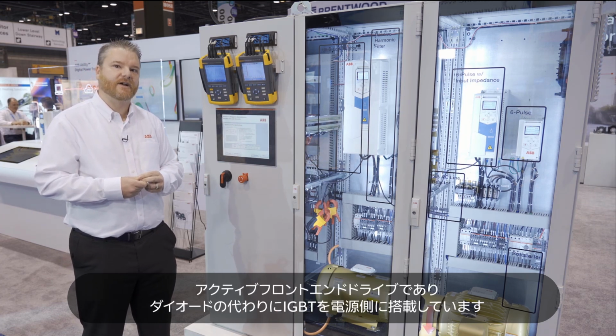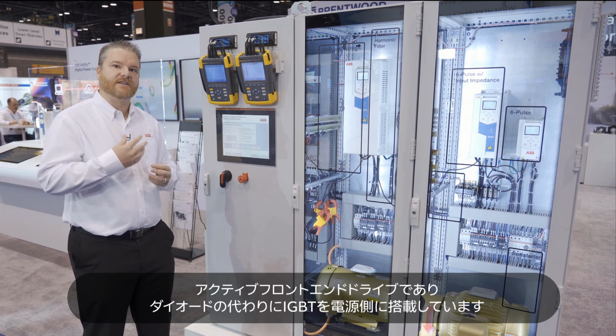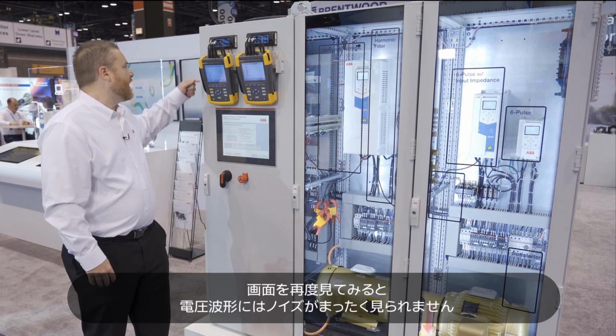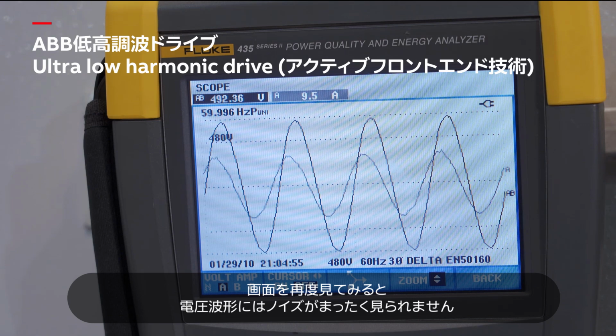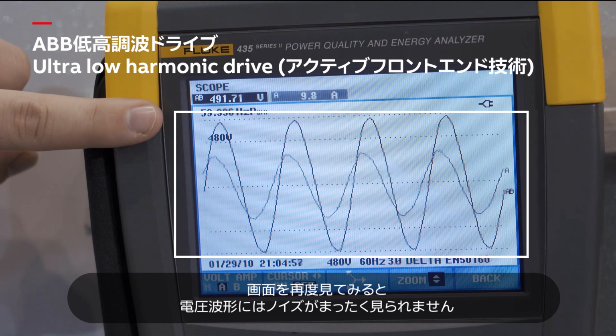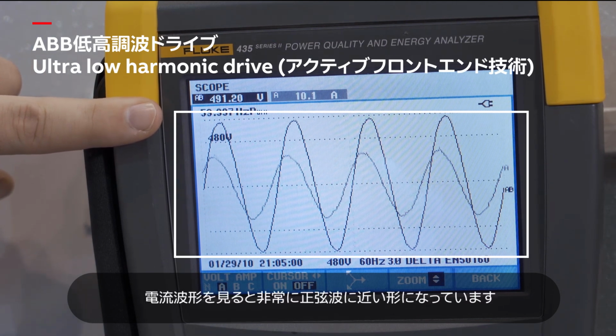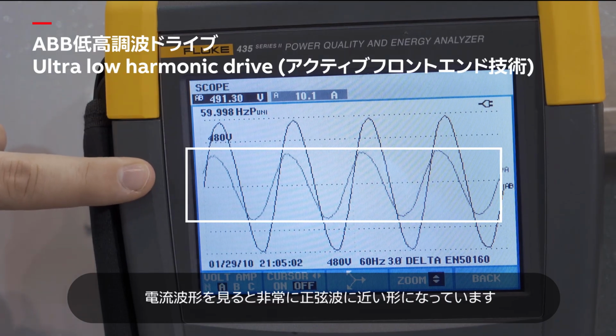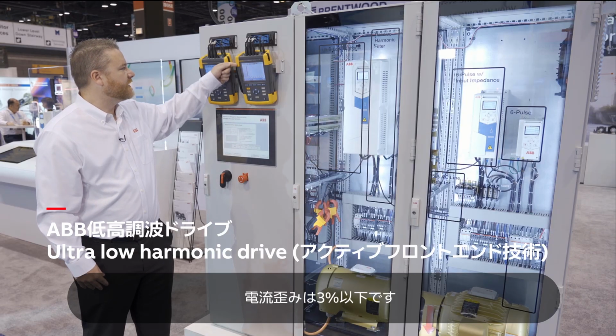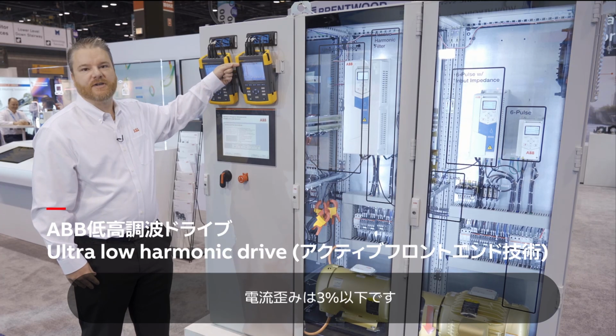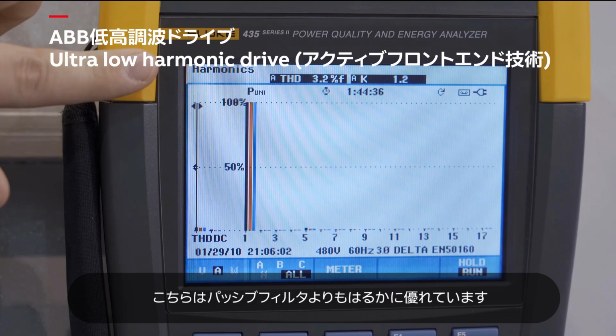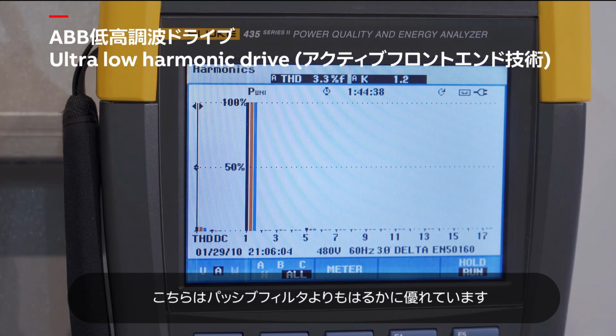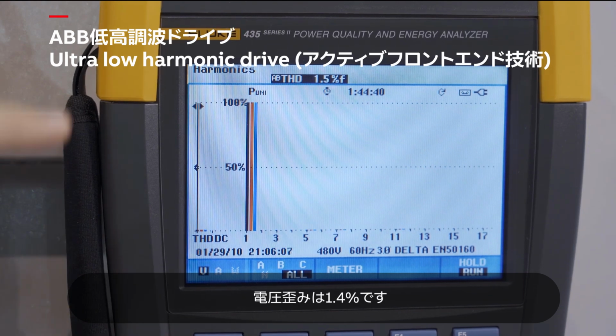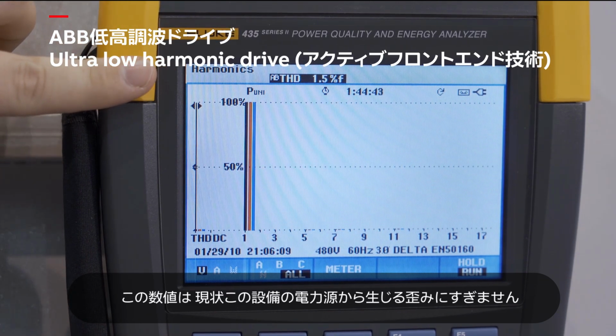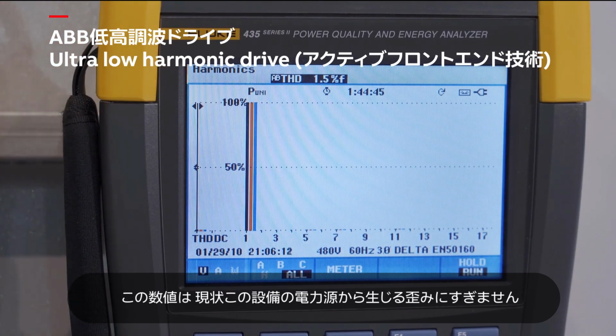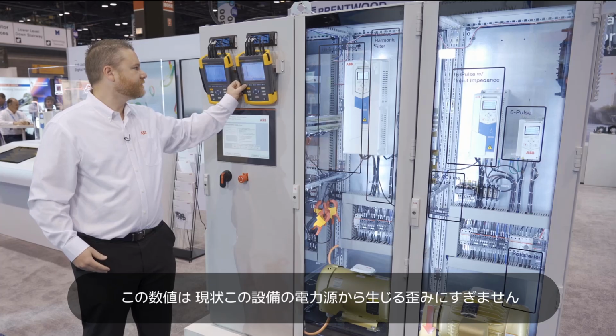This is an active front-end drive. So instead of using diodes, it has IGBTs on the front end. And now, again, looking at the scope image, that voltage waveform, again, no flat topping at all on it. You look at the current waveform, and it's very, very sinusoidal. So now let's take a look at the measurement of that. And your current distortion is 3% or lower. So this is considerably better even than the passive filter. And if I come over and look at voltage distortion, I'm at 1.4%, which at this point is just background distortion from this facility's power supply or power source.